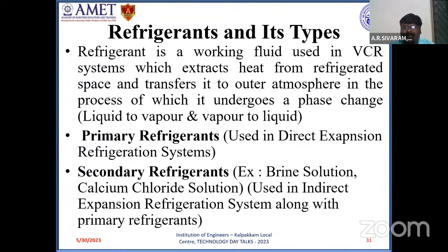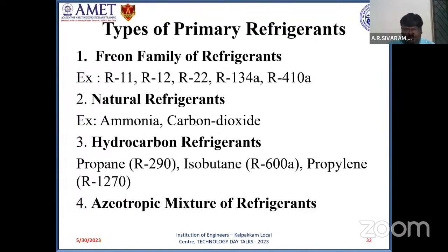So generally, direct expansion refrigeration systems, that is, let it be a domestic fridge or domestic AC, employ only one refrigerant. They are direct expansion refrigeration systems. And indirect expansion refrigeration systems employ primary refrigerants and secondary refrigerants. Most commonly used secondary refrigerants are brine solution and calcium chloride solution. This indirect expansion refrigeration system is normally used in milk chiller plants.